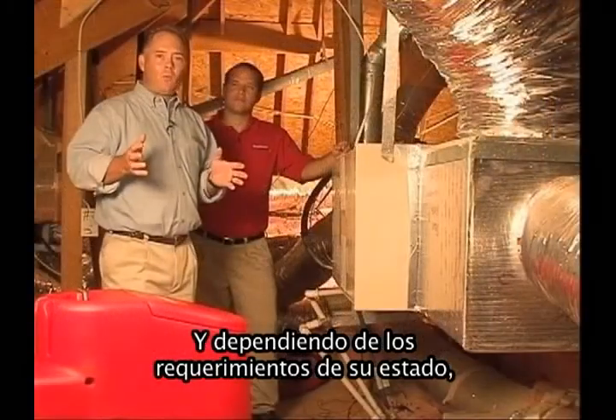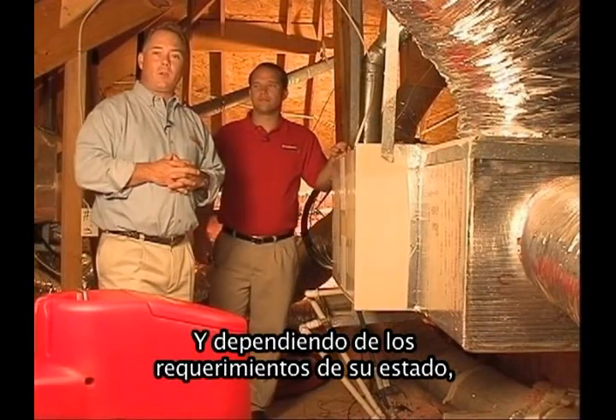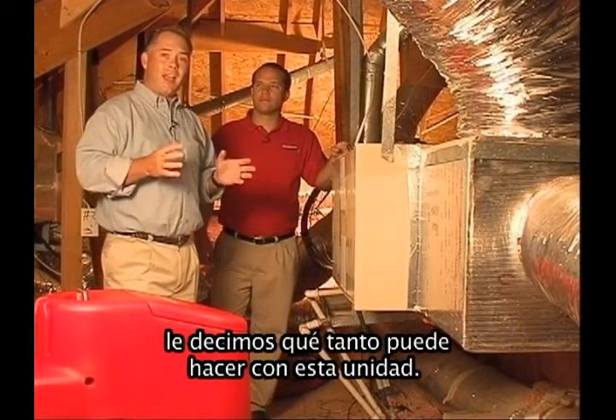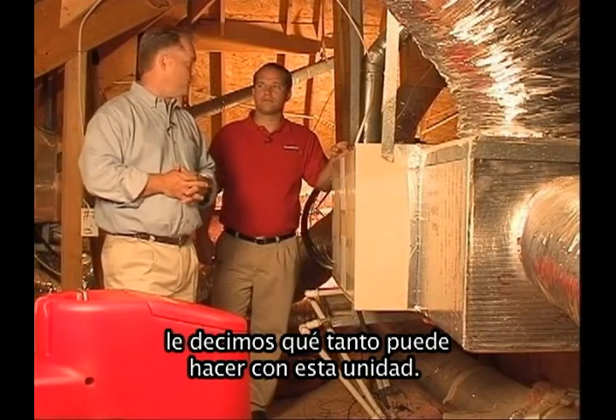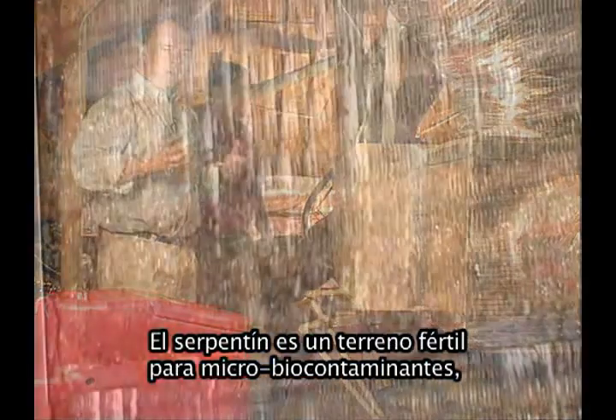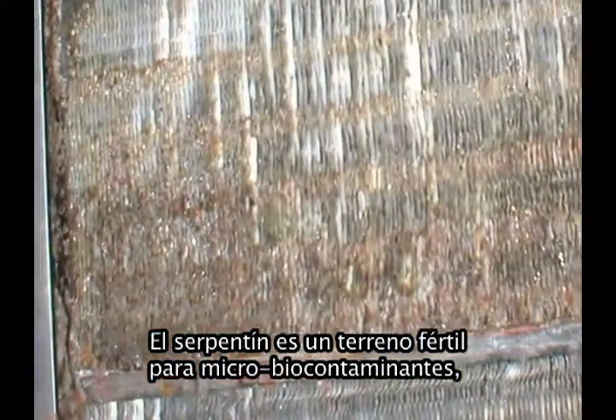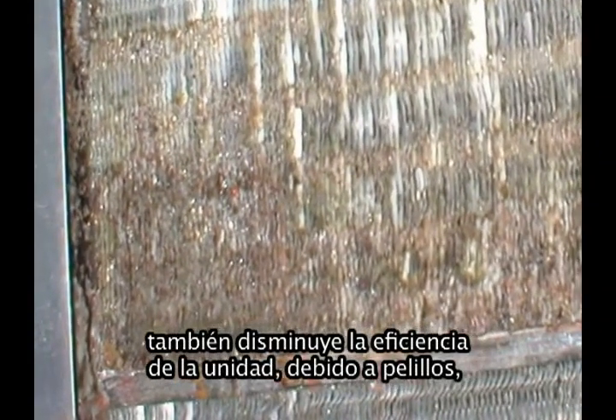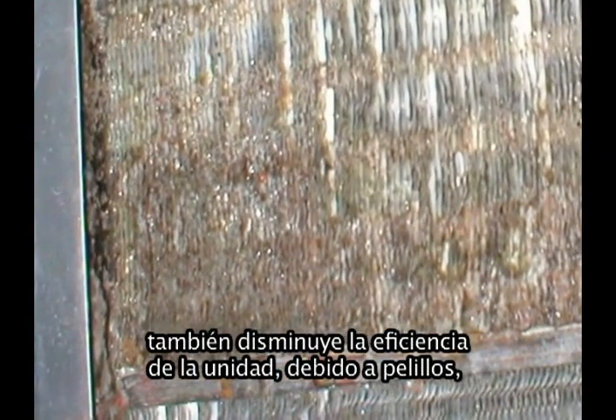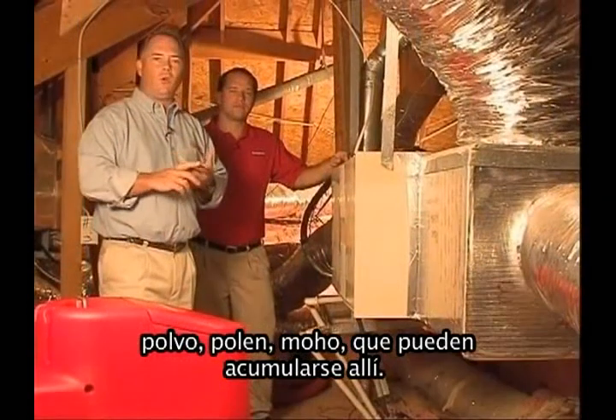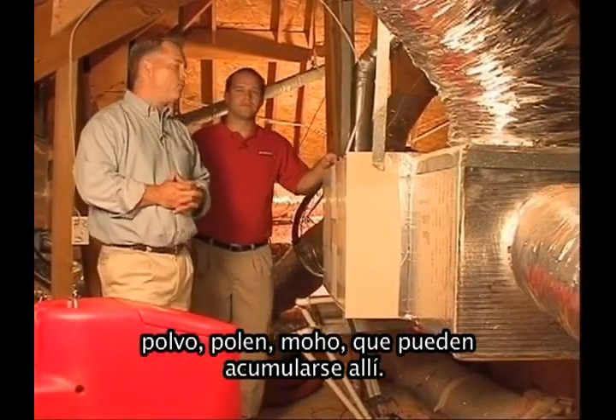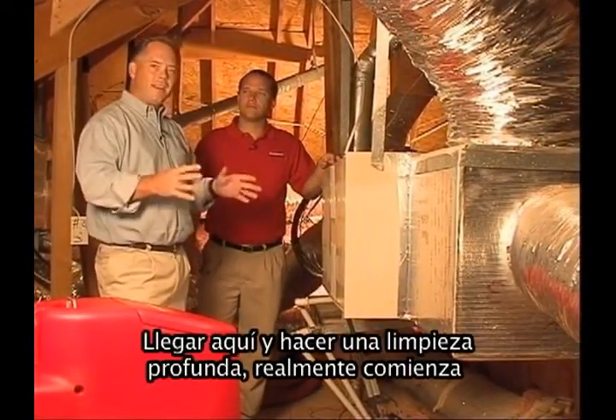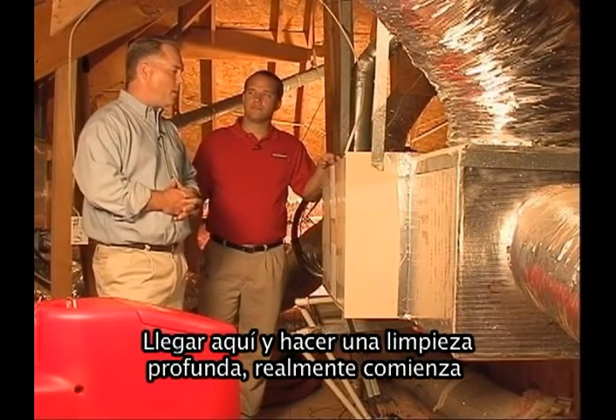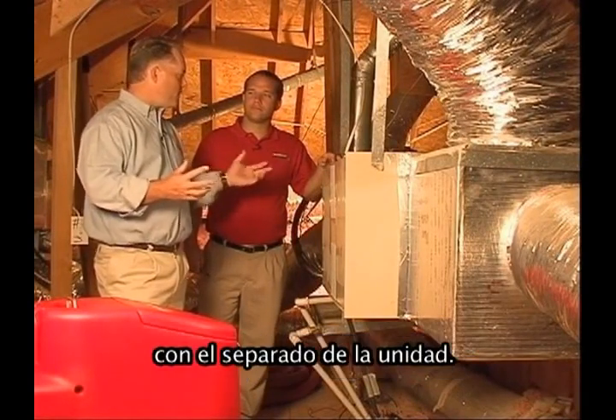And depending upon what your state licensing requirements are will really dictate how much work you can do within the air handler. The coil itself is a breeding ground for microbial contaminants, and it also decreases the efficiency of the unit because of dander and dust and pollen and mold that could accumulate on the coils. So getting in here and deep source cleaning the system really starts with taking apart the air handler.